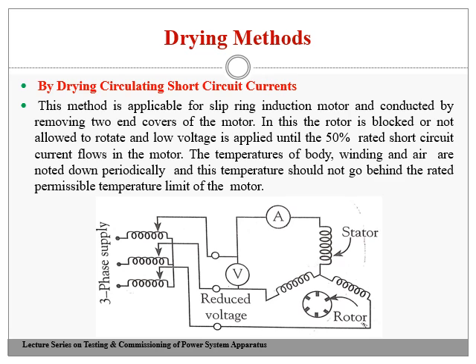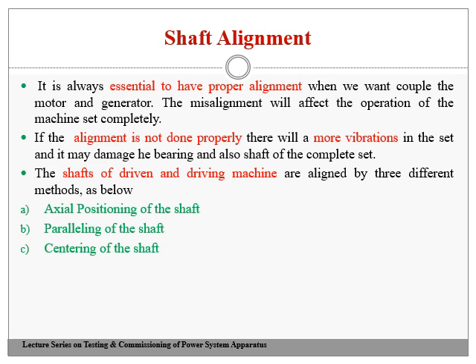Now, this is to be done according to the standards. Sometimes the standards specify what voltage should be given, or what current should flow into the induction motor. Here they say you should apply reduced voltage such that only 50% of the rated current flows. But in this case also, you should take a precautionary measure that the winding temperature developed in the induction motor should not go beyond the value specified by the customer or the manufacturer guidelines. These are the three methods of drying that you see.